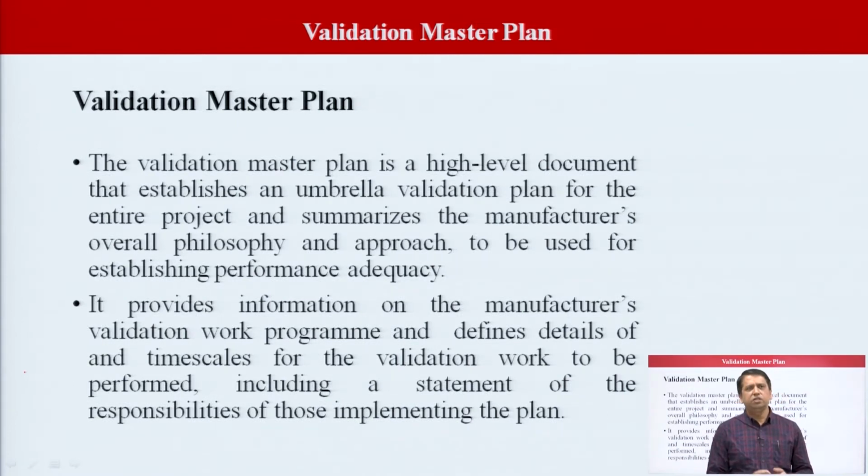Now, what is a validation master plan? It is a high level document that establishes an umbrella validation plan for the entire project and summarizes the manufacturer's overall philosophy and approach to be used for establishing performance adequacy.